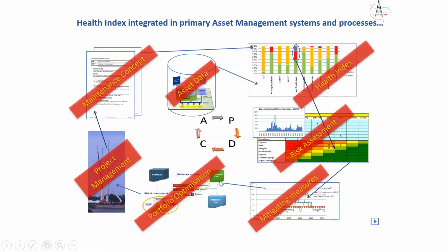For mitigating risk, you have to look at different scenarios, so you make a portfolio, scenario 1, scenario 2, because it's not possible to do everything you want. For example, if a transformer is behaving badly, should I replace it, do good maintenance, do overhauling, run it to failure, or run it at a reduced load profile? You make that portfolio and then optimize depending on the real situation.